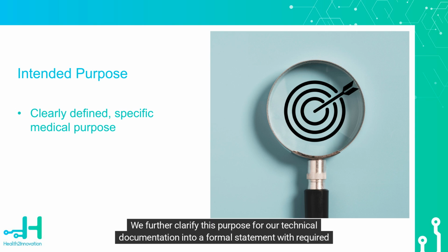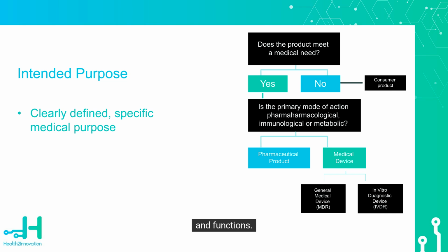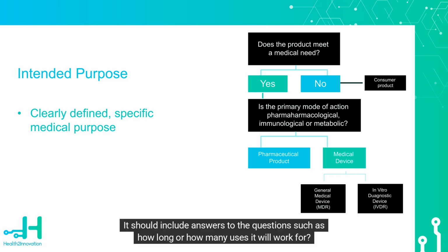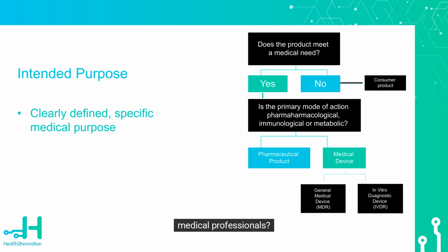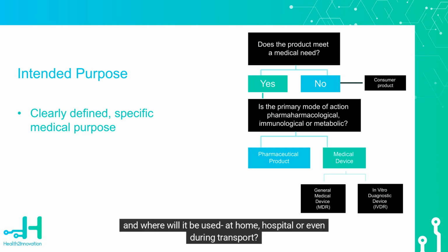For medical devices, we know they serve a medical purpose, and we describe this in our documentation as its intended purpose. We further clarify this purpose for our technical documentation into a formal statement with required details, which is called the intended use statement. This statement outlines not only what medical need your device addresses, but also how it achieves this and functions. It should include answers to questions such as how long or how many uses it will work for. Are the users patients? Medical professionals? And where will it be used? At home, hospital, or even during transport?